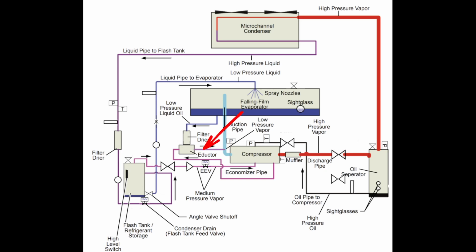And this is where we enter into an oil-laden suction gas that's more of a medium pressure. Okay, so this isn't a true low pressure at this point. It's a medium pressure flowing through here, and that's part of the pressure equalizing process of that low pressure liquid refrigerant mixing with the high pressure vapor gives us a medium pressure return coming back into our suction line.